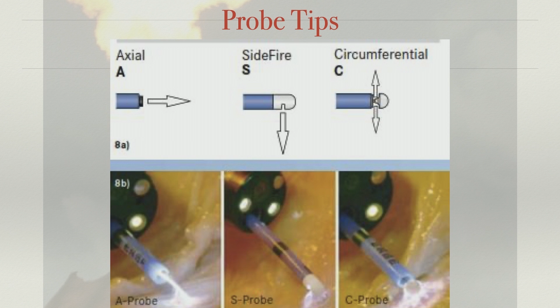While the axial also does a good job, sometimes twisting and turning your bronchoscope can become a problem in difficult areas. But again, like I said, APC has this particular property that it can bend at the surfaces, and therefore it doesn't become a big problem if you have an axial probe as well. So axial and side fire are probably the most commonly used ones during bronchology treatments.